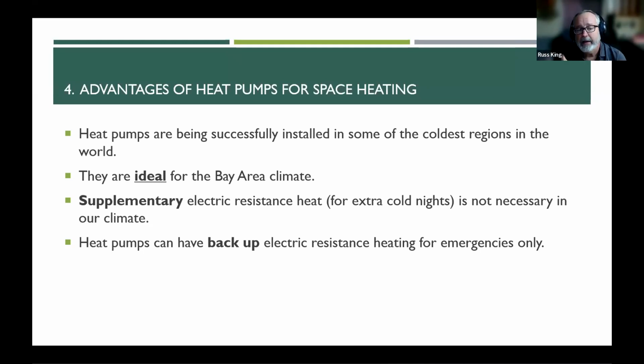Now, you can put electric resistance heating in a heat pump. In some climates they call that supplementary heating. If it gets really cold really fast and the heat pump can't keep up, this electric resistance supplementary heating will kick in and boost the heat pump along. We do not need that in our climate. Heat pumps will keep up if designed properly. That's an important key I'm going to talk about in a minute. Now, you can have what we call electric resistance backup heating, which is only for emergency purposes. Only if your compressor were to fail do you want this heat to kick in. But I would avoid that if possible.